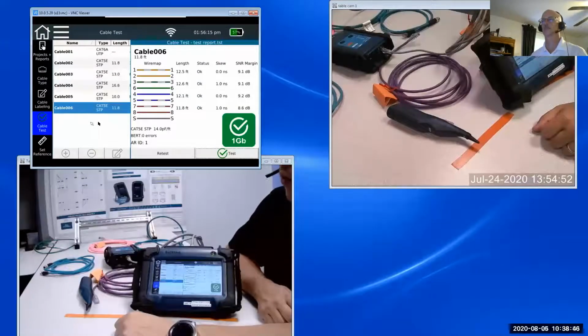Okay, we have a passing 1 gig cable here. It is shielded, and all 4 pairs are wired correctly. I can see the length of each pair and I can see the overall length of the cable, as well as the signal to noise ratio of each pair. And the bit error rate test has zero errors.